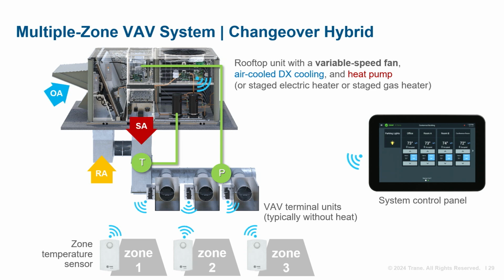In the heating mode, the supply fan will operate at full airflow when the refrigeration cycle is reversed to provide heat. To allow variable airflow to the zones, but full airflow in the rooftop, an air bypass between the supply and return air paths is needed. This bypass will allow excess supply airflow to recirculate back to the rooftop unit. As the zone level VAV dampers modulate farther closed, the position of this bypass damper is modulated in heating mode to maintain the duct static pressure at set point. Due to this bypassed air, the discharge air temperature can become very warm, requiring the controller to limit heating capacity to prevent overheating. So let's return to our branch bank building example.